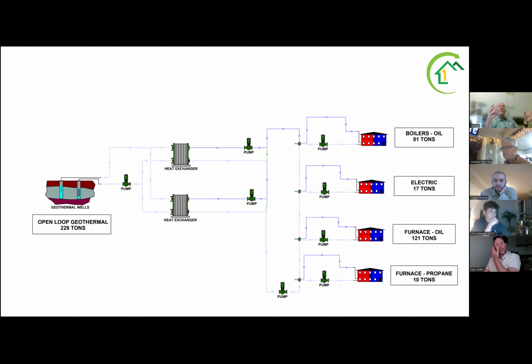So that first question we get is, I don't want to be down the cascade. But it all works out and averages out anyway. We can maintain that loop temperature as tight as 40 to 70 degrees year round, though we like to give it a wider band, because the electricity deficit from running the pumps too hard doesn't pay off in overall system performance. The wider we can keep that temperature band, the more efficient everybody operates. So yes, it is an ambient temperature loop, and your heat pumps are designed to extract and reject energy to it, and that's all there is to it.